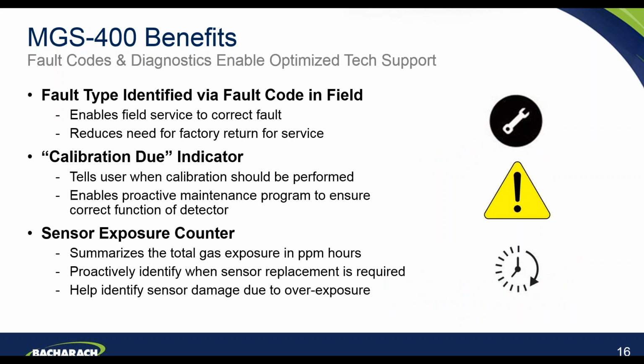Built into the MGS-400 series, we have also included some fault codes and diagnostics, and this is really designed from an engineering standpoint to optimize technical support. So it helps the engineers to identify quickly and easily what the actual fault is or could be, and it helps therefore to potentially reduce that need to return any detectors to the factory for service. It helps to identify the fault quickly and therefore minimize downtime on site of the detector.